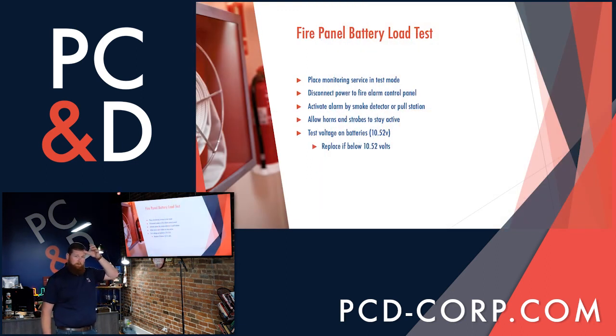All right, over to the fire panel. Typically you have 2 12-volt batteries located within your fire panel, and those batteries are made to produce the electricity needed for your fire panel, strobes, and the annunciators in case power were to fail within your building. A couple of years ago, it is required by the NFPA that the 2 batteries, individually, cannot drop below 10.52 volts when in use.